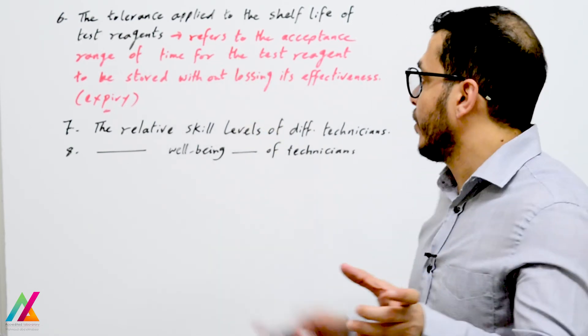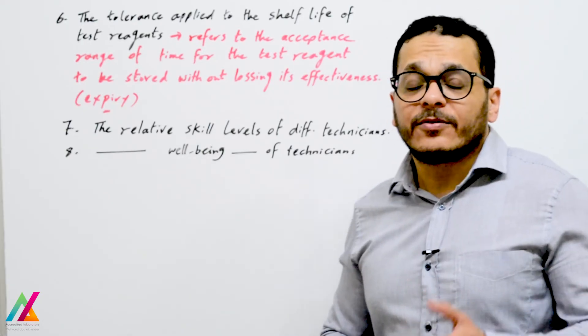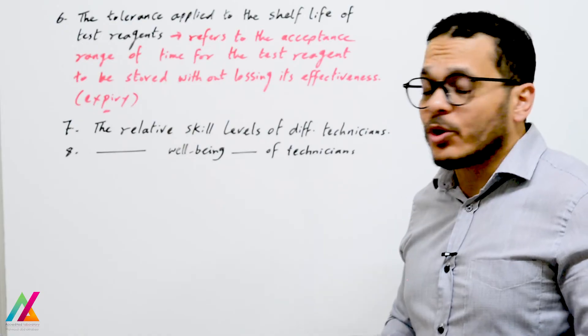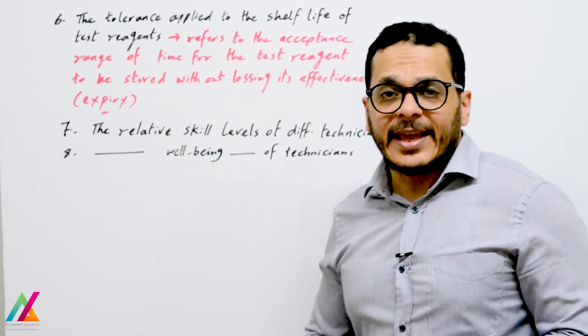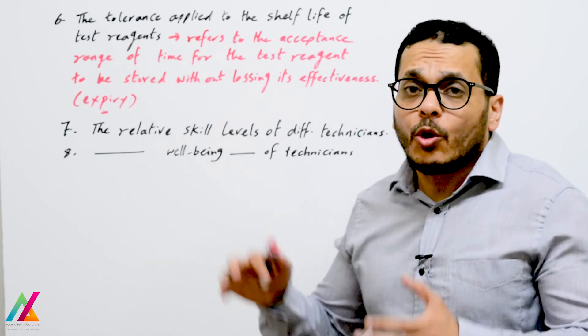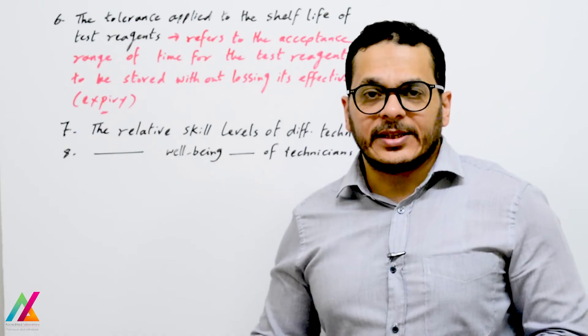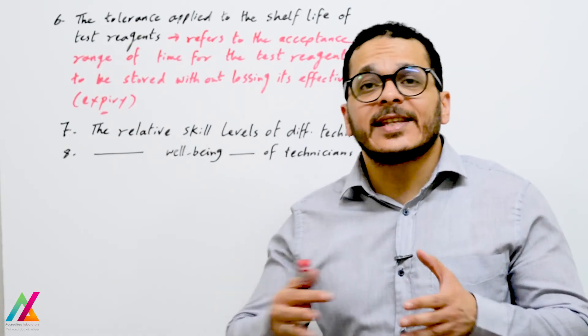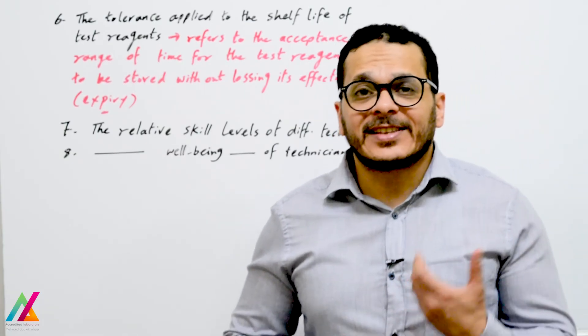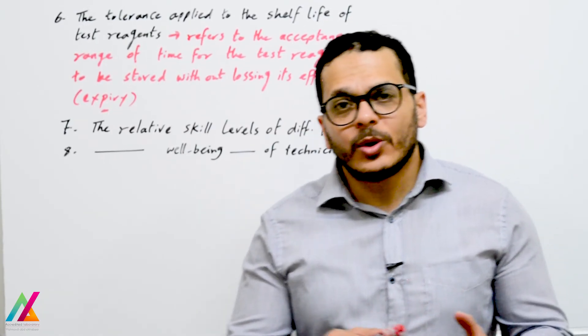The tolerance applied to the shelf life of test reagents — the acceptance range of time for a reagent to be stored without losing effectiveness — is also a source of uncertainty. The relative skill levels of different technicians and the competency of personnel, as well as the well-being of any technician undertaking the analysis, can all affect measurement results and must be included when calculating uncertainty. This can be captured through reproducibility — repeating the analysis different times by different analysts over a long time scale. These are examples of biological, instrumental, and personal bias that affect the accuracy, precision, and certainty of microbiological tests.